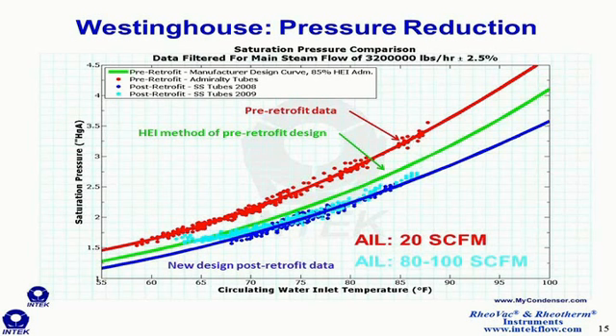Any increase to that air in leakage, say going from 20 up to 25, increases the back pressure in the condenser immediately. But after the retrofit is installed, after we get rid of those blue regions in the bundle, we concentrate the air to the new air removal sections that are installed via the retrofit. That condenser is able to handle much more air in leakage with no back pressure penalty. And so all of that teal data shown on the plot is data obtained when the unit is operating with 80 to 100 SCFM of air in leakage.